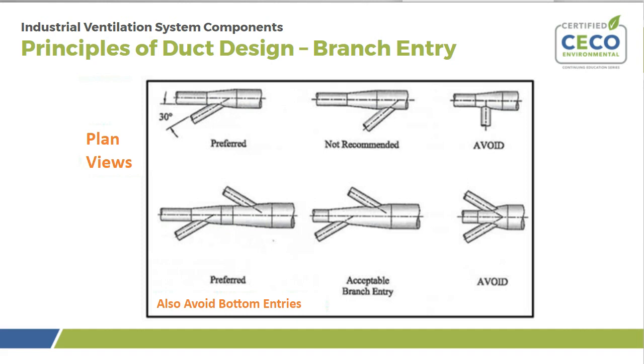When you bring 2 branches in to your trunk line in the same vicinity, you want to stagger those to get proper blending of the airstream, like you see in the left and center. The right, you want to avoid that, because even though the areas of those 3 ducts are equivalent to the larger diameter, it's going to set up more turbulence, and you're going to get some really strange wear effects in the duct just beyond that fitting. So you want to make that nice preferred 30 degree or 45, whatever, but not 90.